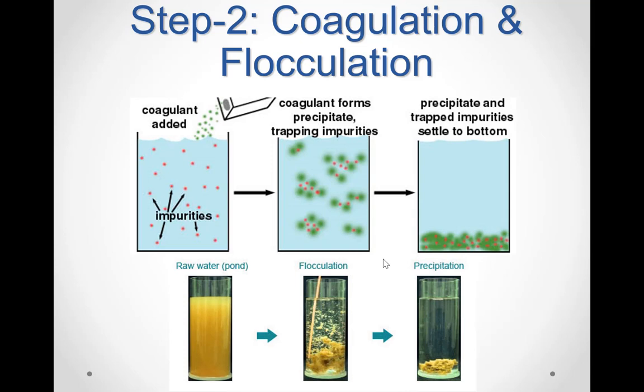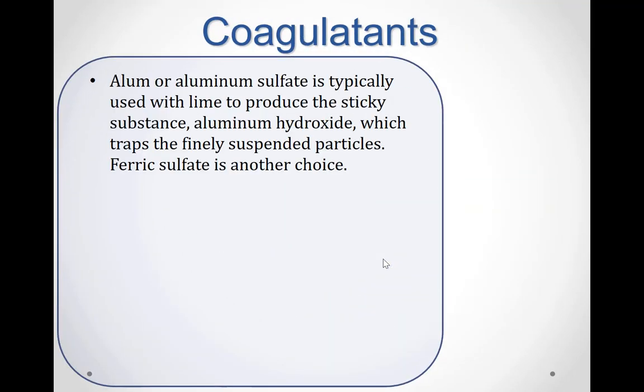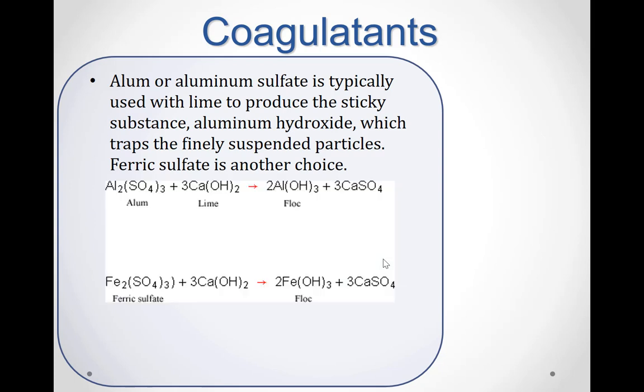Step two of the water treatment process is coagulation and flocculation. Chemicals with a positive charge are added to the water. The positive charge of these chemicals neutralizes the negative charge of dirt and other dissolved particles in the water. When this occurs, the particles bind with the chemicals and form larger particles called floc. To encourage increased floc production, gentle mixing is utilized. Coagulants can be poly aluminum chloride, aluminum sulfate, or ferric sulfate. For example, with aluminum sulfate, if you add lime or calcium oxide, the reaction will form aluminum hydroxide.